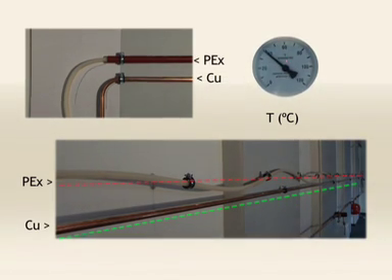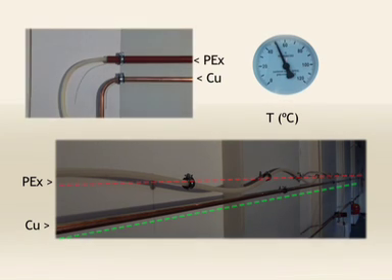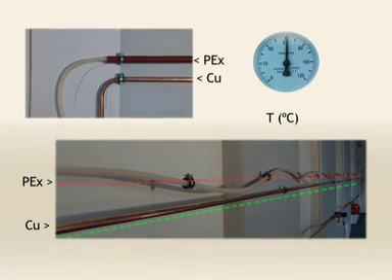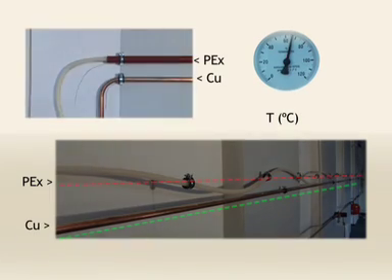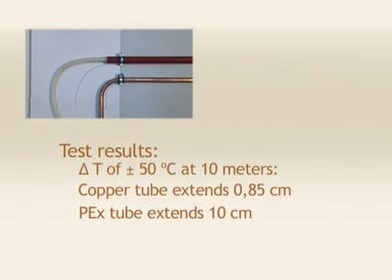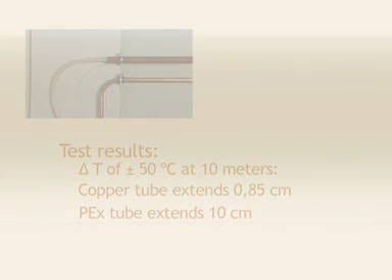At a temperature increase of 50 degrees Celsius this results in an expansion of less than one centimeter. With polyethylene we have 10 centimeters of expansion. This expansion shows us the necessity of very large expansion legs for polyethylene. If not, the pipes will bend, possibly damaging the installation.